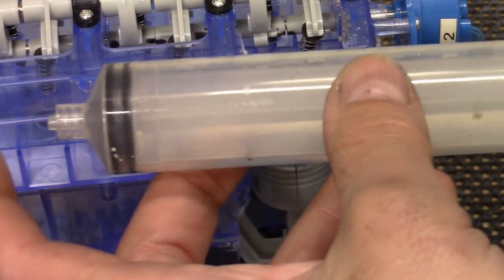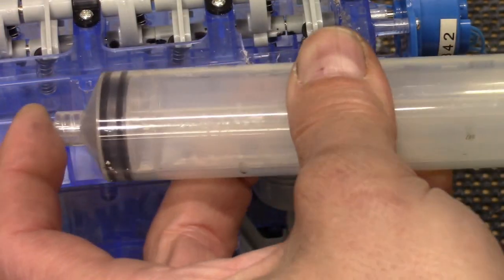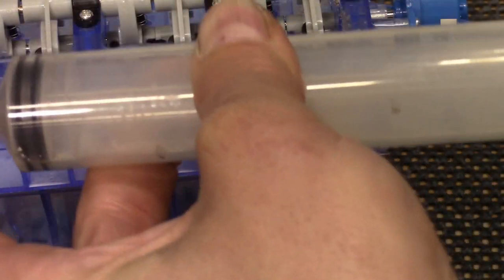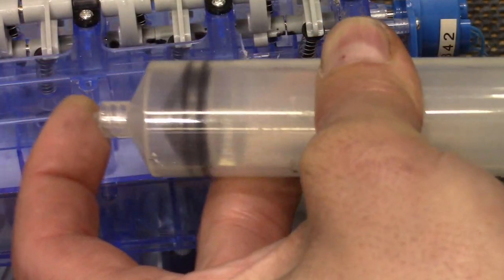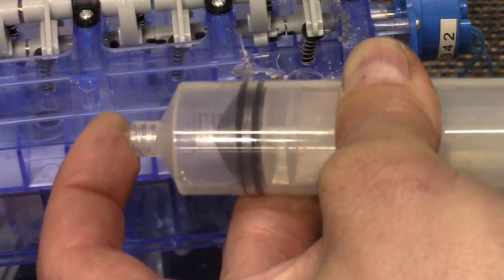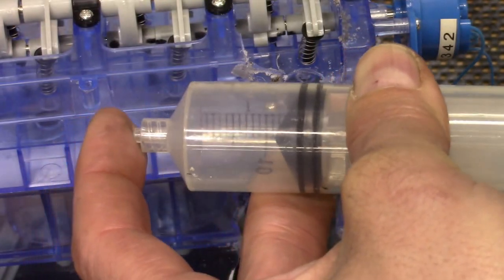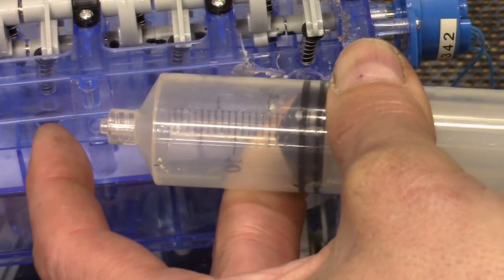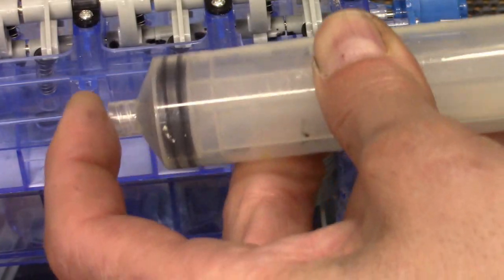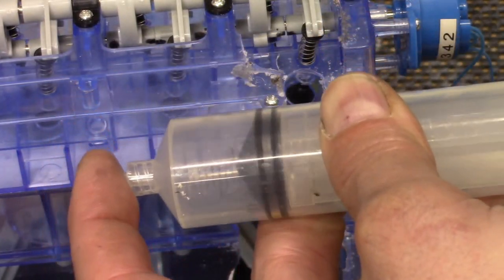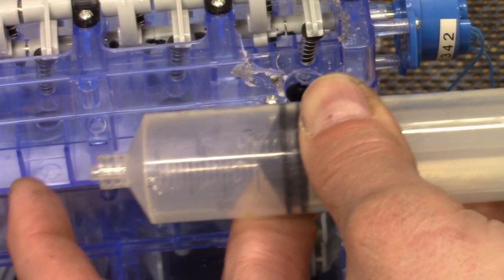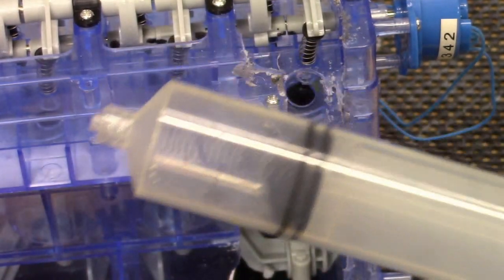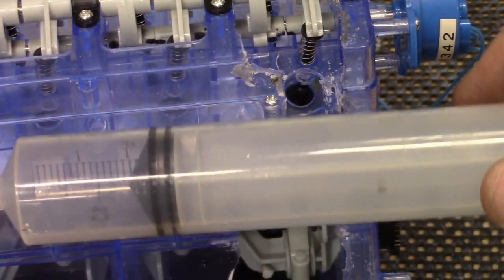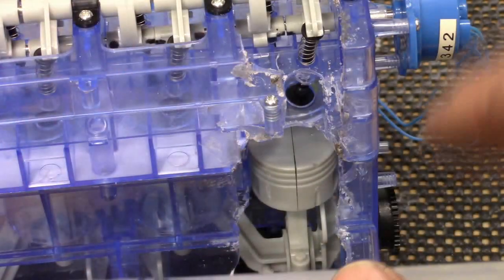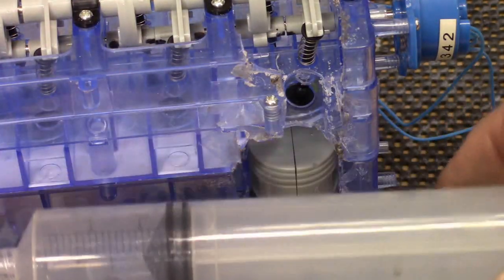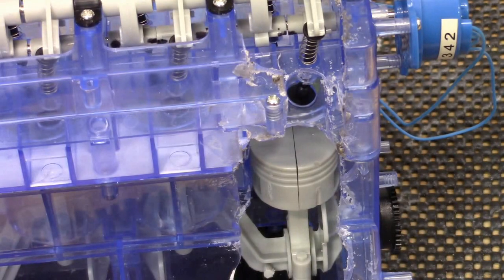Just like with this syringe here, if I plug the end of the syringe because the valves are closed, and I pull that syringe, there's a lot of vacuum there that wants to suck the syringe back. But if I open up my finger, well, then we lose that vacuum. Just that brief amount of time that I let off, you can maybe hear it, and I lose that vacuum. That's still a matter of microseconds, but we're going to be able to see that actual loss of vacuum again when that valve opens on our pressure transducer data.